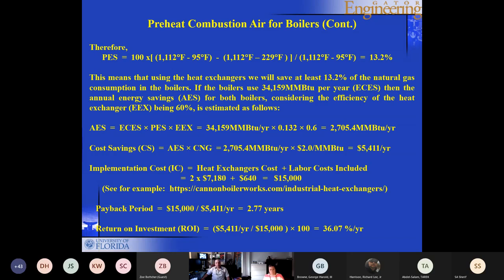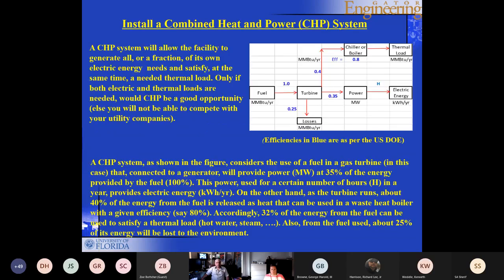And the implementation cost would be the cost of the heat exchanger plus the labor cost associated with installing the heat exchanger. We can figure 2 times $7,180 per heat exchanger plus $640 for labor. And we can get the payback period by dividing the total cost, which is $15,000, by the $5,411 per year of savings that we had, which gives 2.77 years. And then for the return on investment, you take the reciprocal of 2.77, multiply by 100, and you get 36%. So that's one other thing that can be done. And I believe this is the last one.